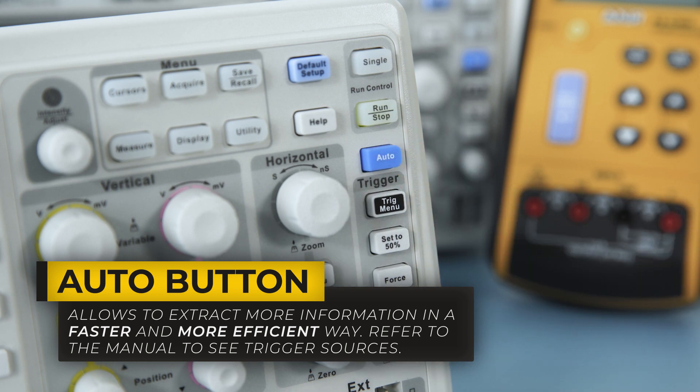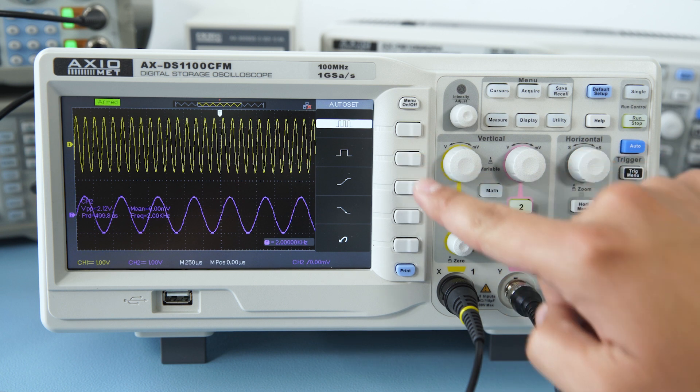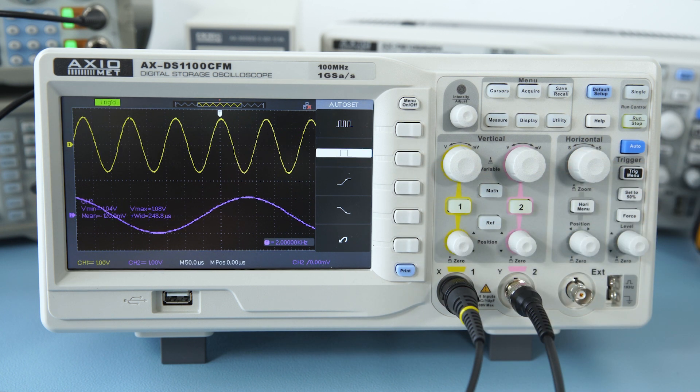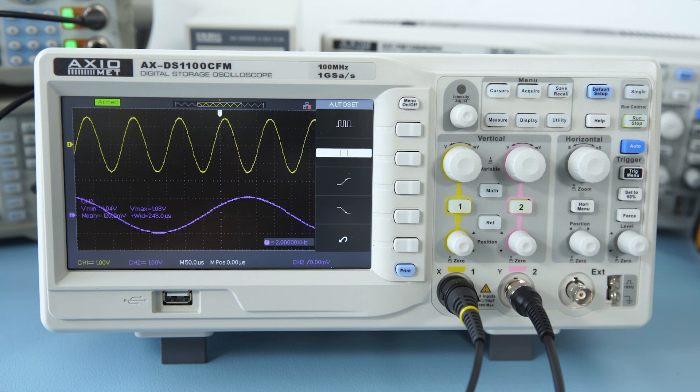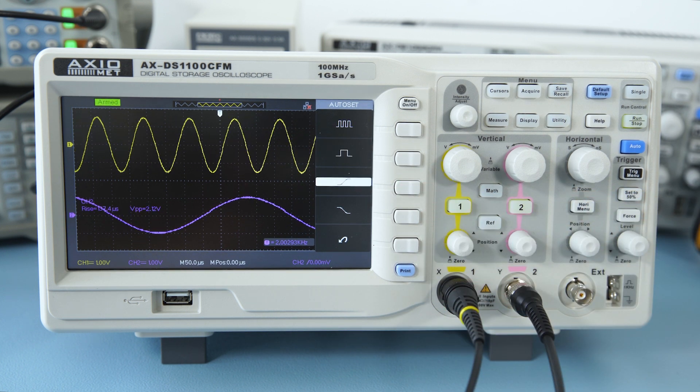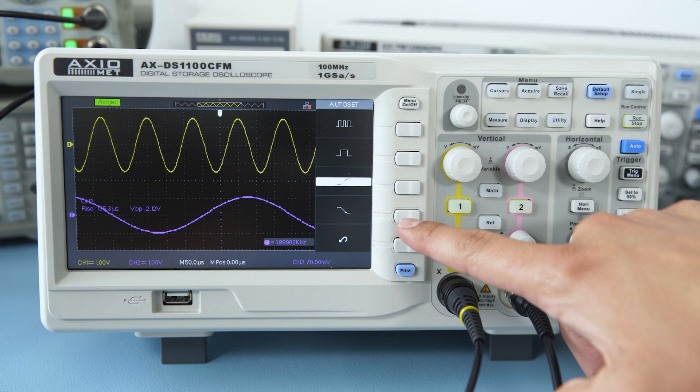In order to extract more information in a faster and more efficient way, press the Auto button. The Oscilloscope will automatically detect the optimal vertical and horizontal scales for both channels and will display a readable signal. Moreover, it can display just a single cycle over its rising or falling edges.